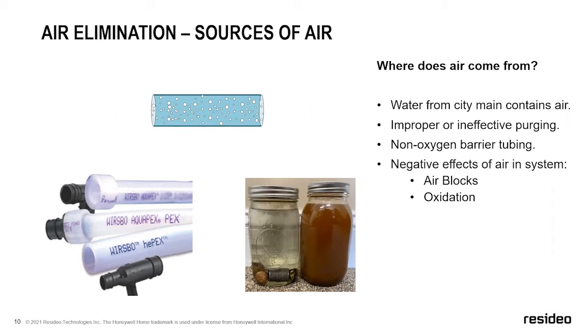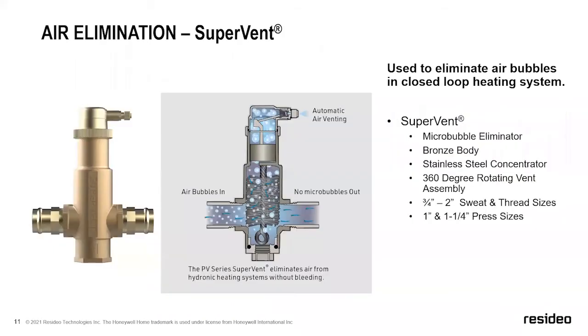I also want to bring up, if you do run into systems where, let's just say AquaPEX or a plumbing PEX was installed, you will need to install a stainless steel circulator. You can't use our standard pumps because they are cast iron. That cast iron will rust out essentially. So something to take note of is not only do you have to take care of the air bubbles, but if you do have the wrong type of PEX, you've got additional complications you're going to have in that system.